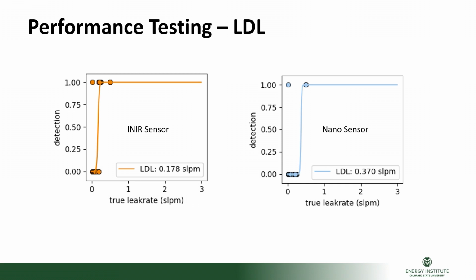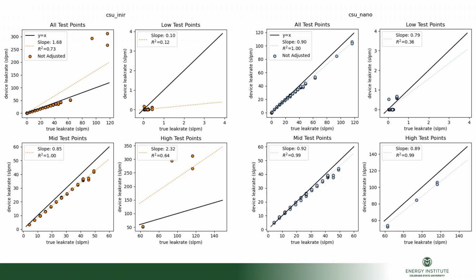And note that here we're just looking at a 50% probability of detection, not a lower limit of accurate and useful quantification. We also did that, but we have that on a different slide. You just take a linear regression of the lower points and then use 3 times the standard error of regression for that. That's in the final report if you're interested in that. And a bunch of data plots.